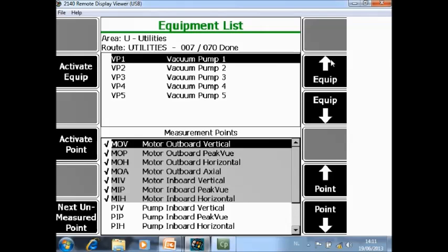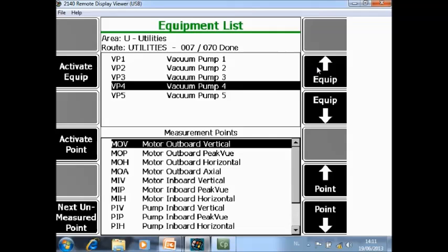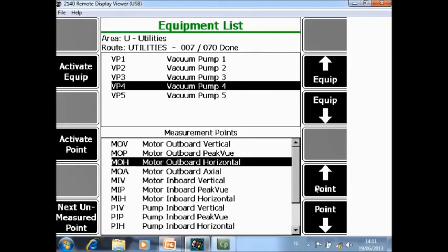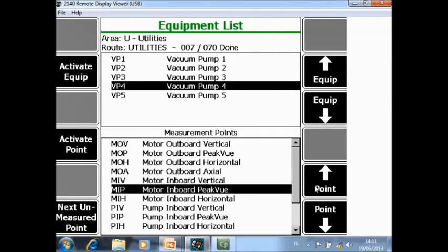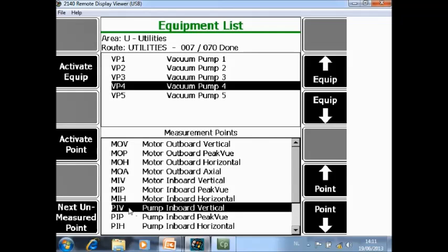If a machine is completely measured you will see a check mark in front of the machine. With F8, F9 you can navigate between machines and with F11, F12 between points. I've selected machine 4, measurement point pump inboard vertical. If I push activate point I will jump inside the route immediately to this point.